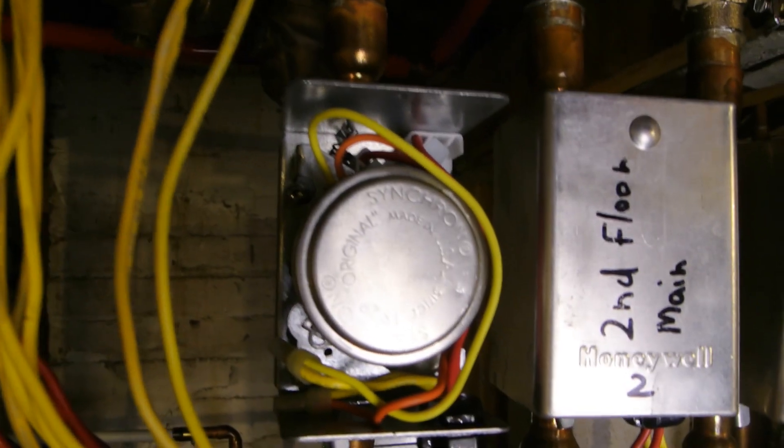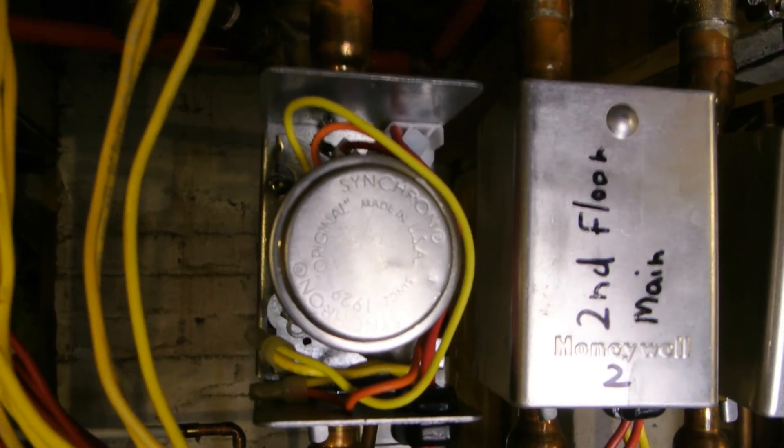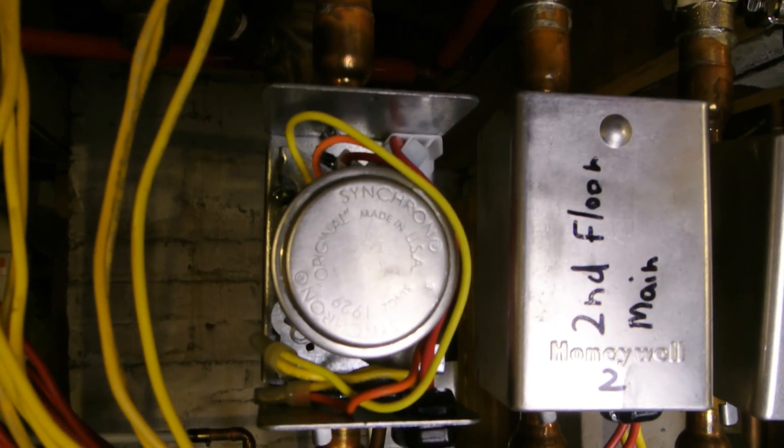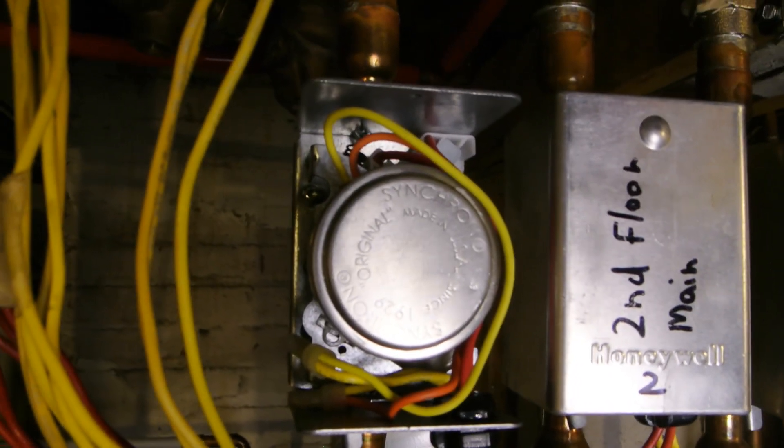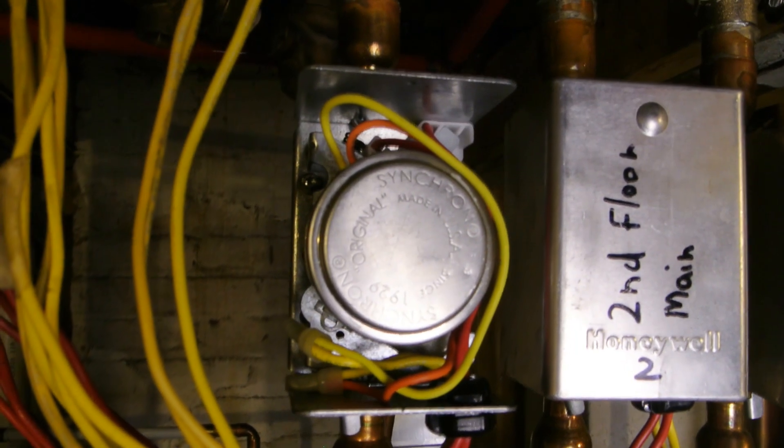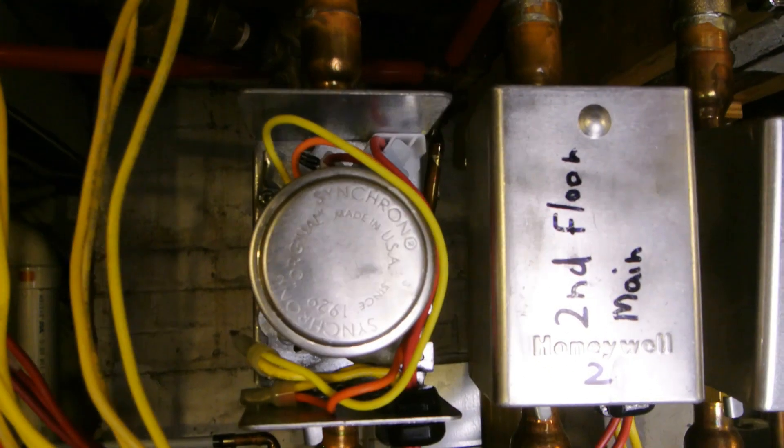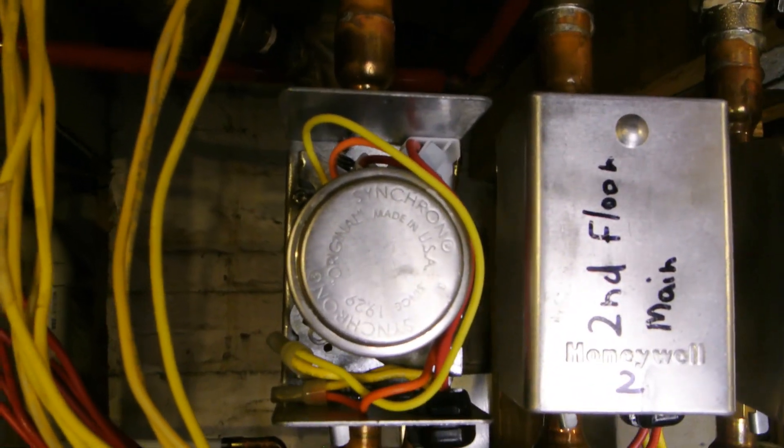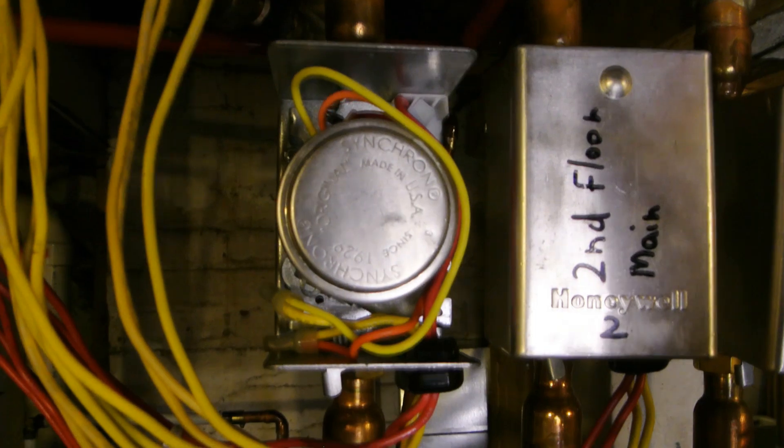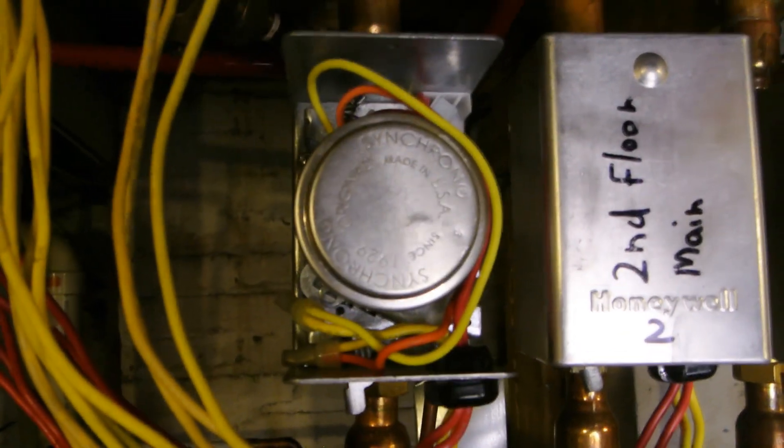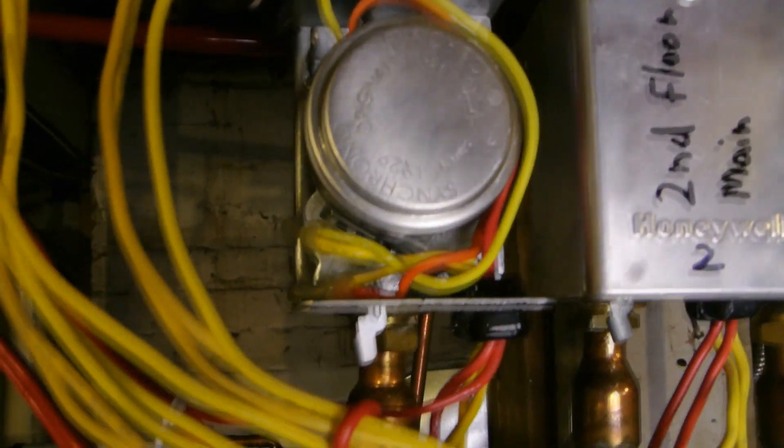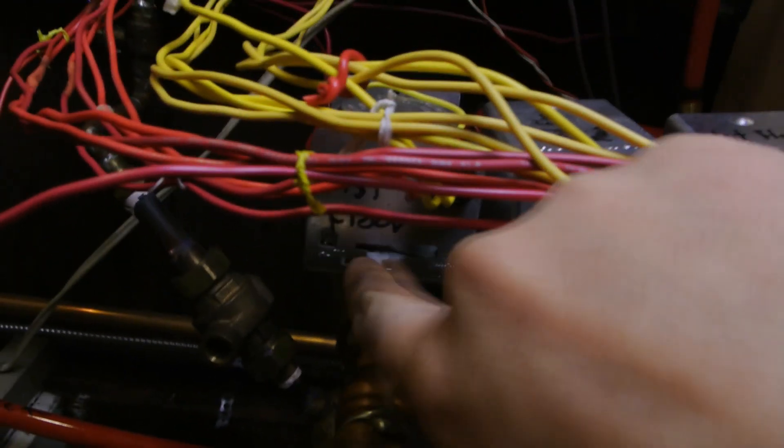I'm going to take a valve apart and show you how it completely works because I have a few that I switched out previously because they failed. The most common thing to fail is either the power head, which is this electrical motor, or the end switch burns out through contact and shorts out.